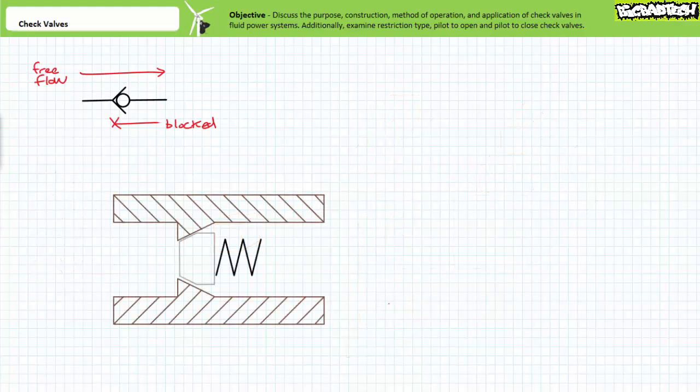Returning to the intended topic of this lecture, check valves are extremely simple valves. The cutaway view of a basic check valve shows a movable poppet that fits into a seat machined into the valve body. The movable poppet may or may not be held in place with a light biasing spring.